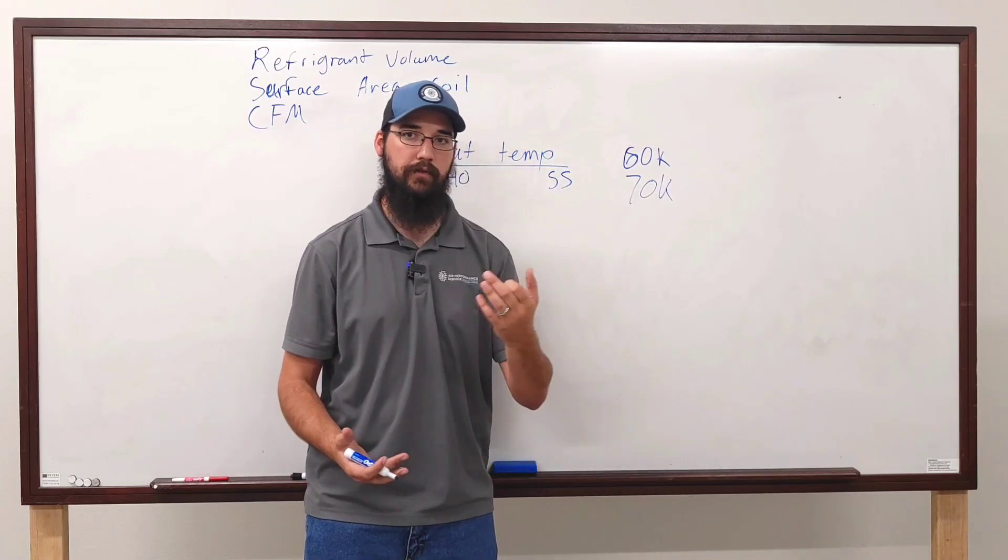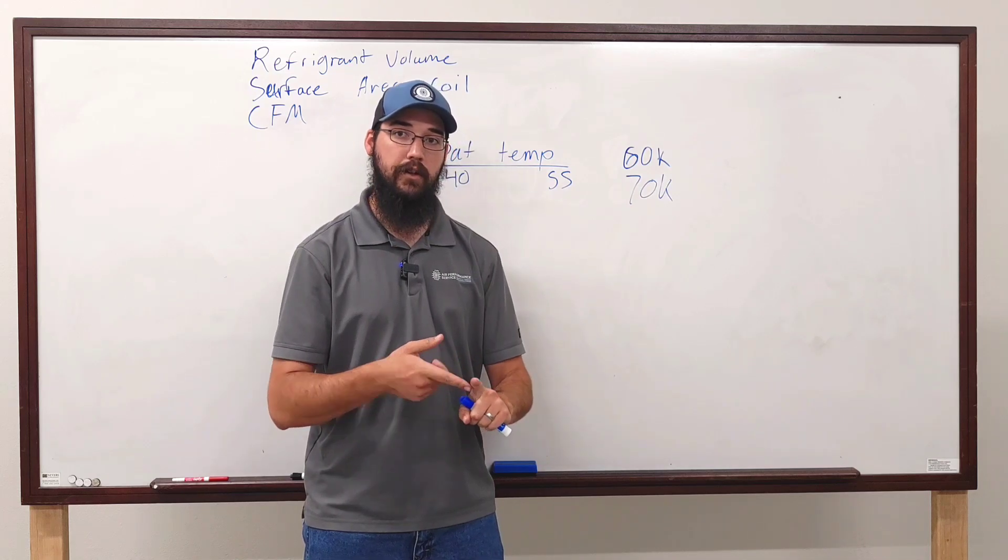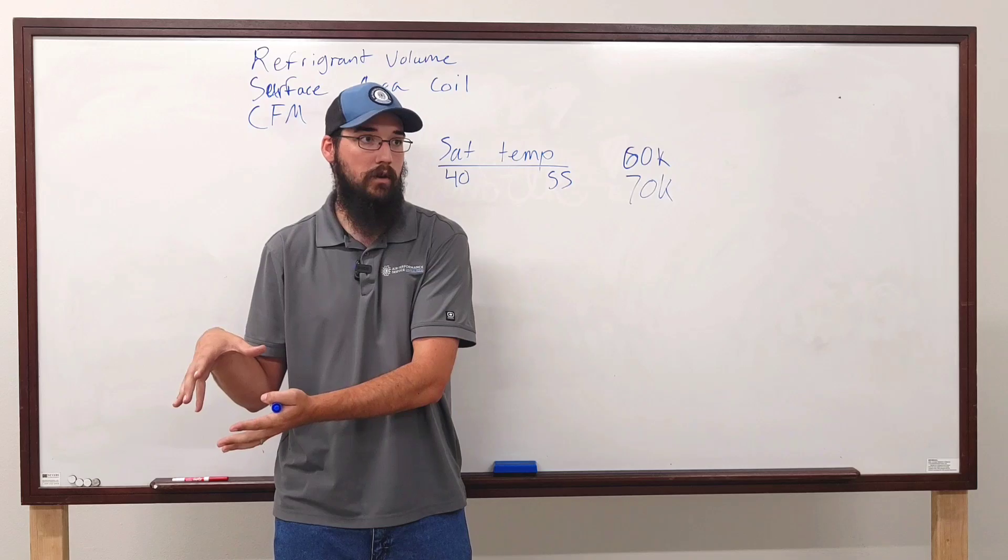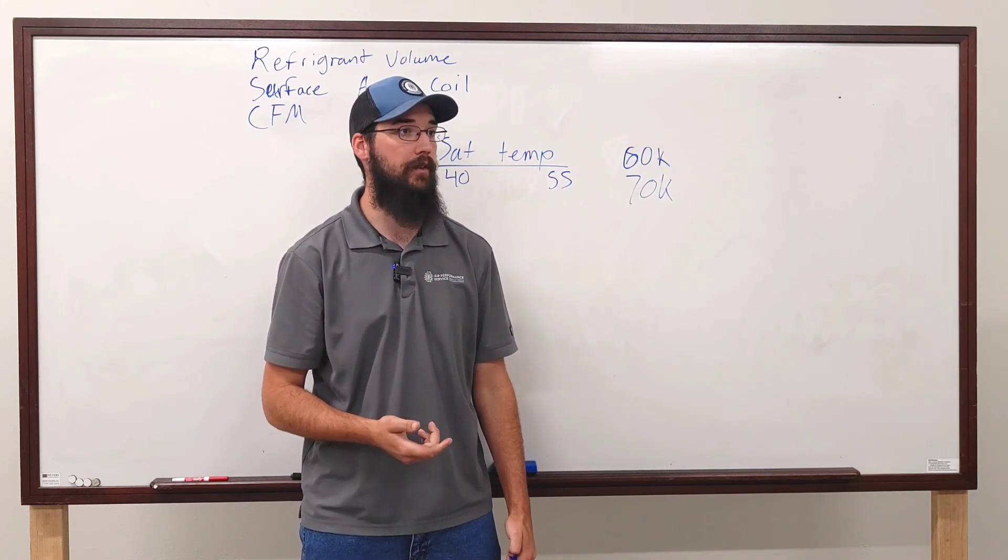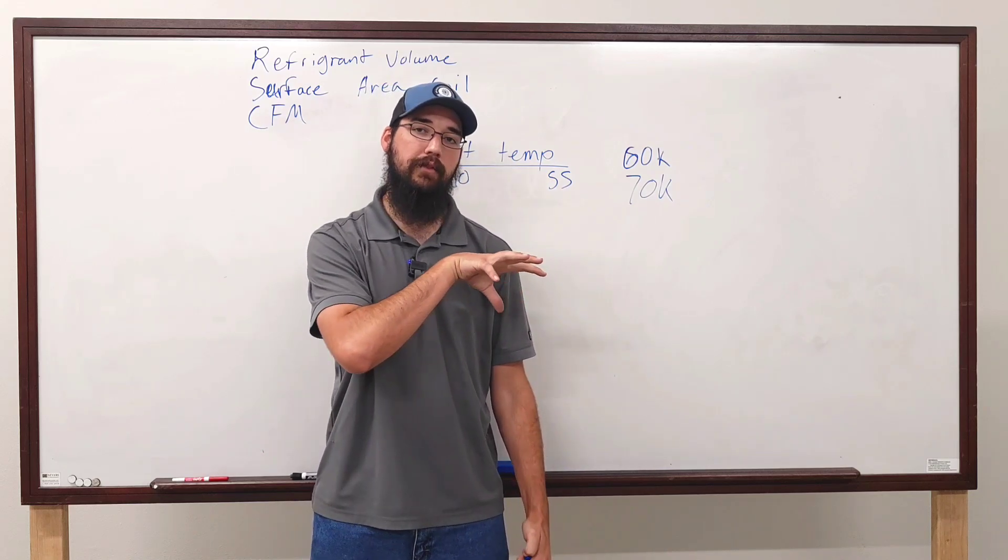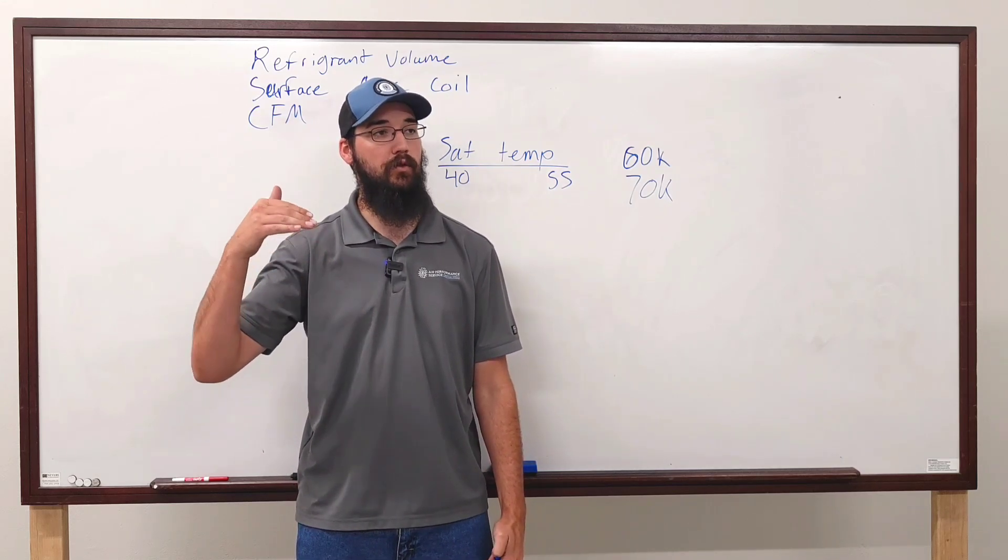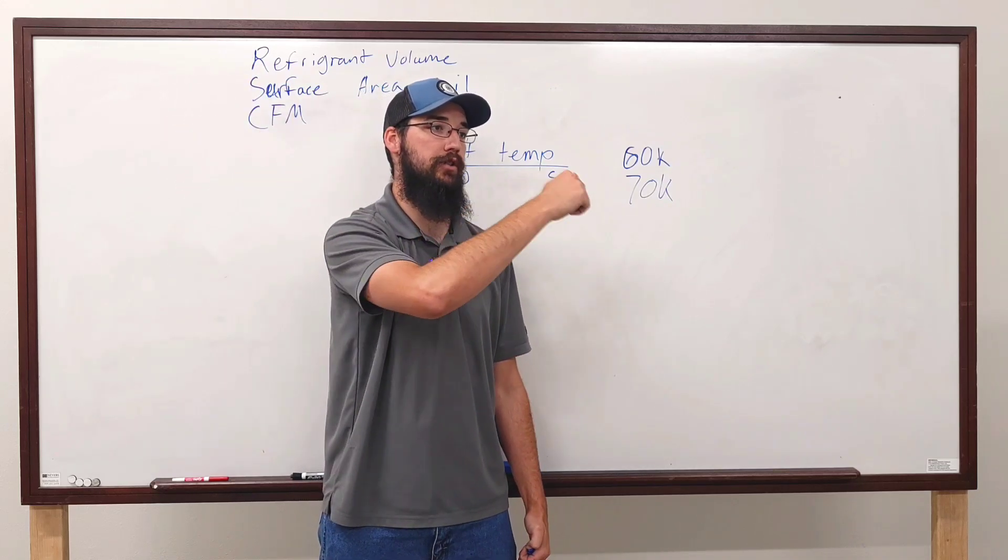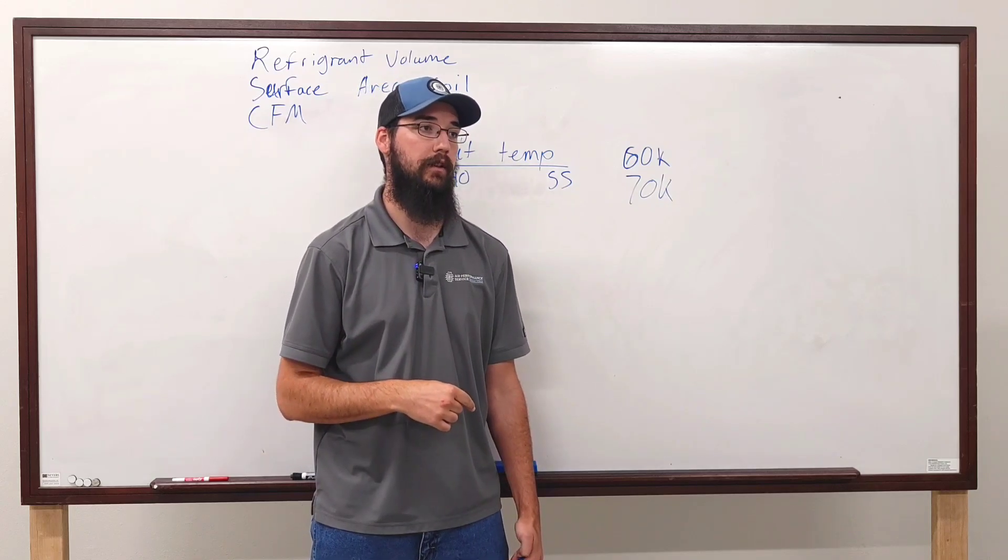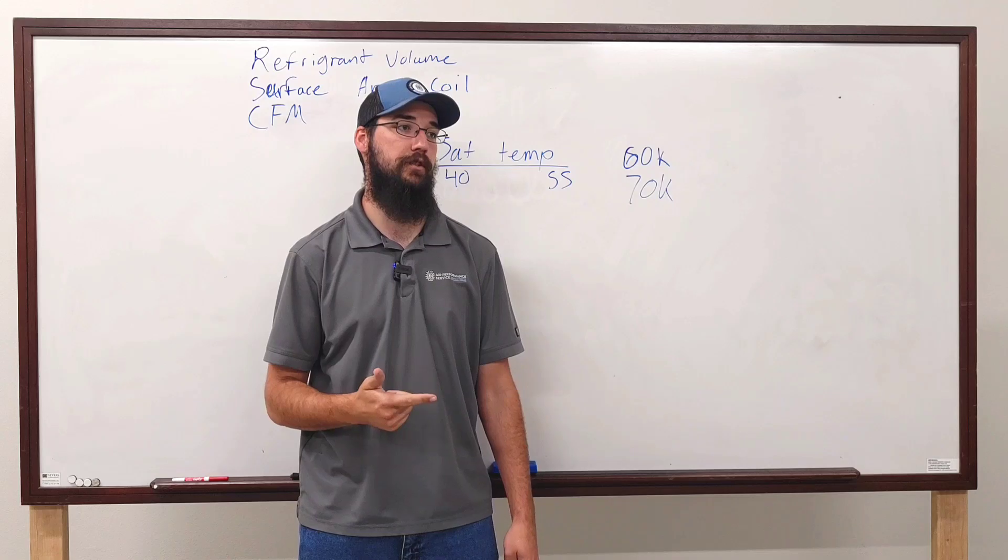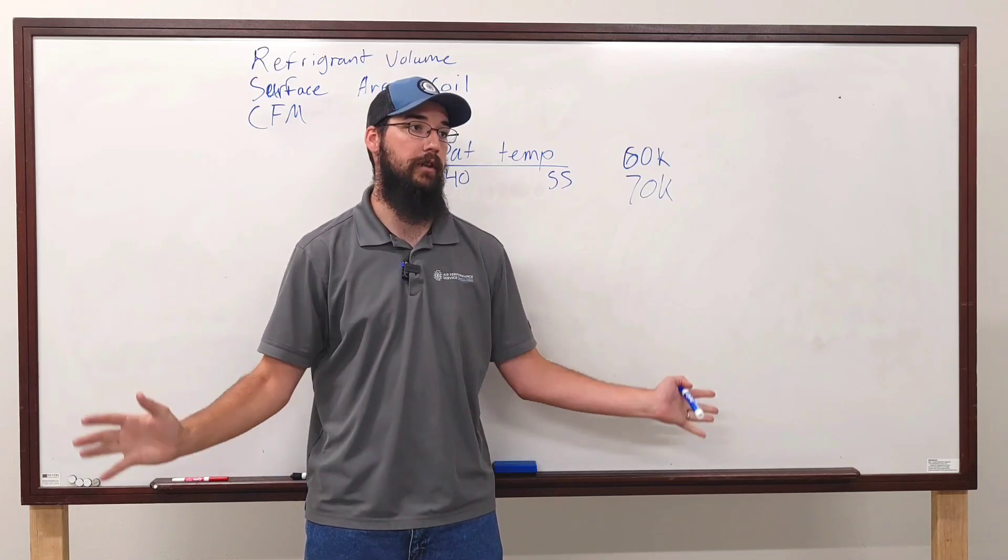They do the same thing with cooling towers. Cooling towers have to be sized so much above what the equipment itself is rated for. So we got a chiller, for instance, or self-contained water source heat pumps, you name it. Additional loads in that loop can be the pumps themselves. That pump running is generating heat, even if the motor's outside of the water loop, which usually it is. But that pump itself is generating a lot of heat. Stop flowing water on a pump one day and let it sit long enough, that thing will get burning hot. So you have that, then you have the friction of the water moving through the pipes. I've had loops get to over a hundred degrees because the equipment shut down on a chill water loop, because the equipment shut down and the pump was allowed to just run on its own without anything cooling it. Just the friction of the pipe and the pump itself was enough to raise that water well over a hundred, so far over a hundred that it ruptured all of the thermometers on the loop.